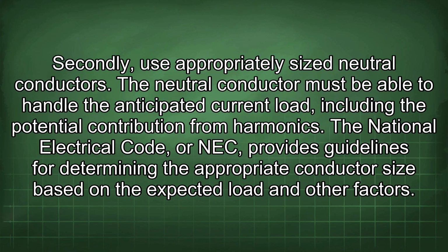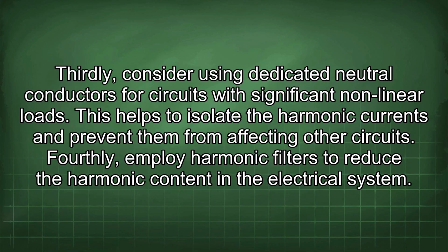Secondly, use appropriately sized neutral conductors. The neutral conductor must be able to handle the anticipated current load, including the potential contribution from harmonics. The National Electrical Code, or NEC, provides guidelines for determining the appropriate conductor size based on the expected load and other factors. Thirdly, consider using dedicated neutral conductors for circuits with significant nonlinear loads. This helps to isolate the harmonic currents and prevent them from affecting other circuits.